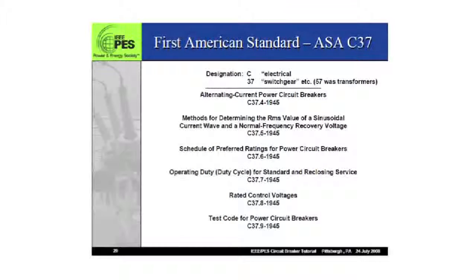It's historical, for the reason that they started then: the C letter stands for electrical, and the 37 was for switchgear. It's no longer really valid that much — in fact, 37 is also used for protective relaying. That's also a protection device, but it's not a circuit breaker, it doesn't interrupt any current, it's a logic device, an electronic device. But it also falls under C37, so it's sort of a historical reason.